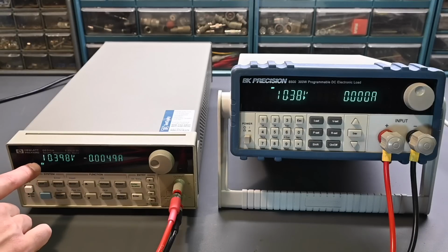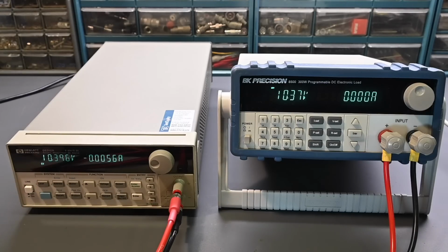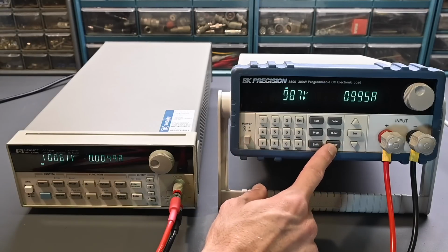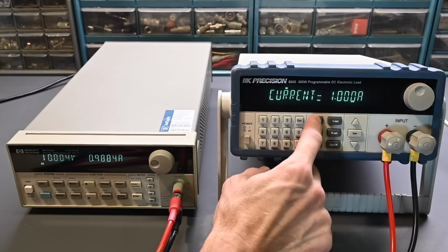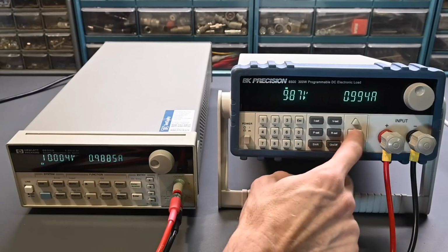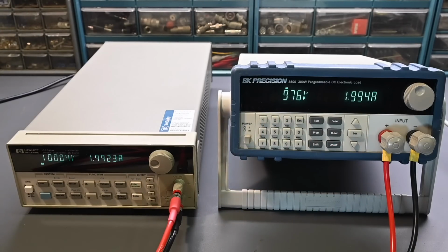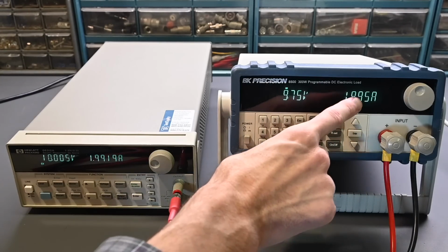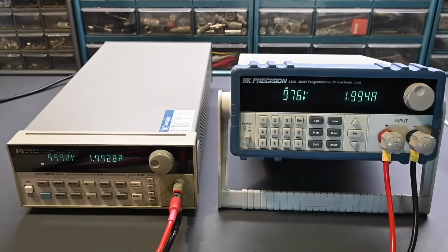But anyways, now it's back in the constant voltage mode, a little bit over 10 volts. If we go back over here to turn this on, let's try current set 2 and enter. Okay, now it's allowing that, so those are looking very close, 1.99, this is 1.99, so right at 2 amps. It's holding at 10 volts, so it's able to output the full amount of current, full rated current. There is not a problem, and the voltage settles in, but it's not really stable, it's still hunting around. So yeah, it definitely has a voltage regulation problem. Looks like that's where the issue is at.